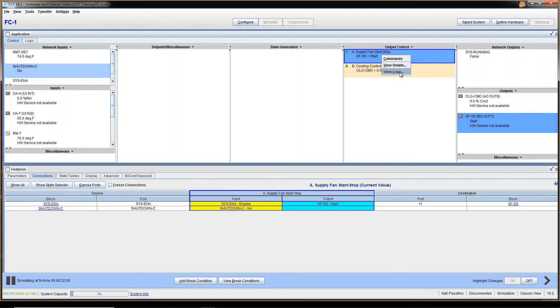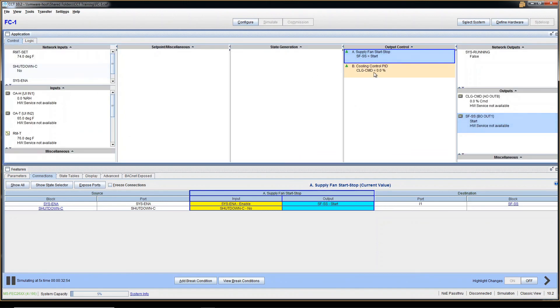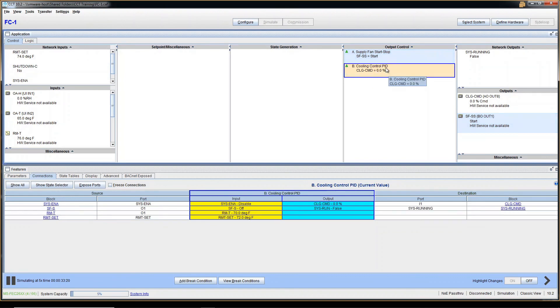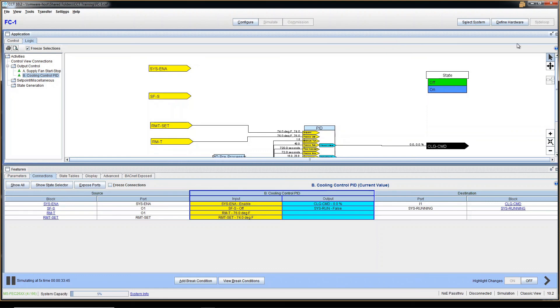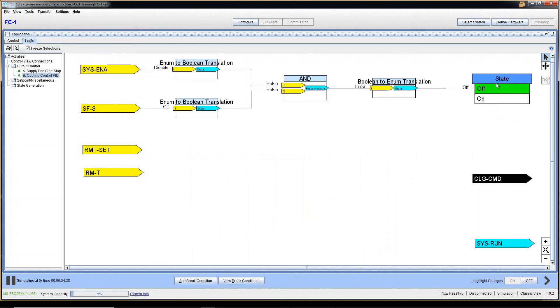The fan will run. If I right-click and view the logic, you can see both conditions are now true. Coming back to the next module programming block — in the logic you can see enums being translated into Boolean so they can go into a logical AND block. Then if the result is True, it converts back to an Enum — an Off/On enum output. That's the overall pattern: Enum in, translate to Boolean for logic, translate back to Enum for outputs.